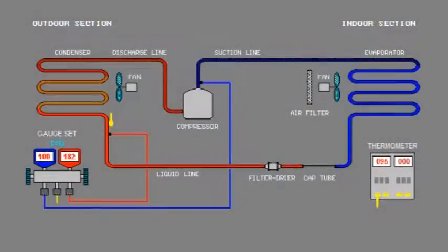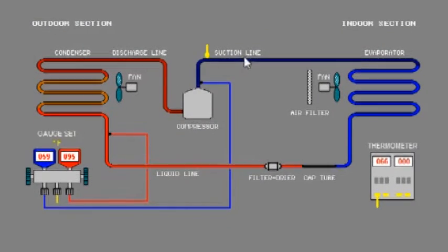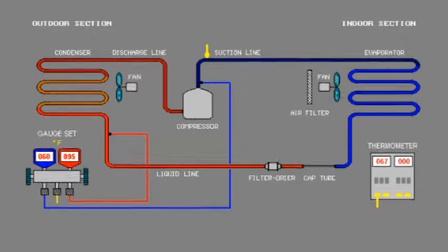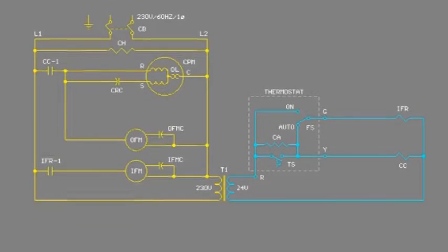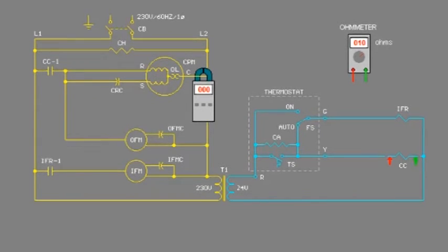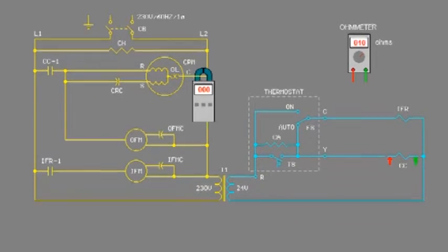Now, he just installed a set of gauges. Now he's going to calculate subcooling. Now he's installed a thermometer lead on the suction line to calculate superheat. This is a very important step in the troubleshooting process when diagnosing mechanical refrigeration problems. Next, he'll go to the schematic diagram where he will use the voltmeter to check voltage on his compressor. Next, he will use his amp meter to check the amperage on his compressor. And finally, he'll turn the power off and use his ohm meter to check the resistance in the contactor coil.